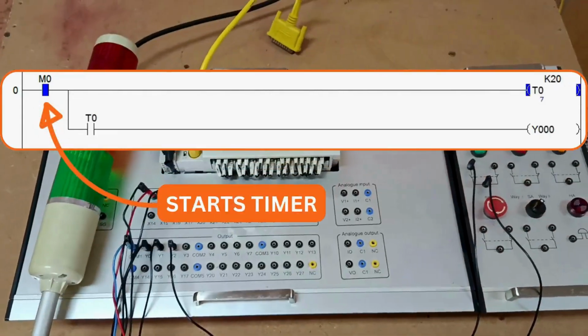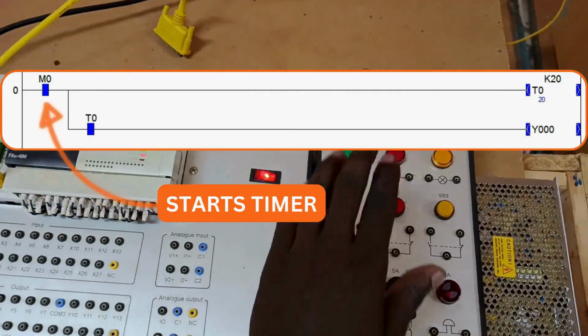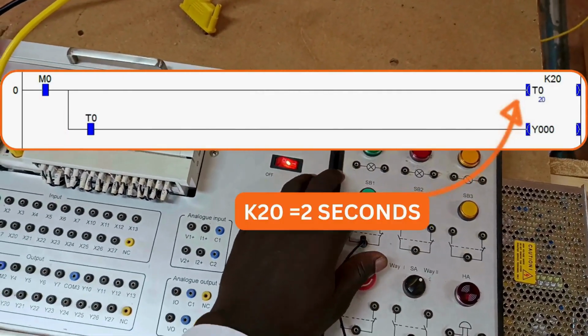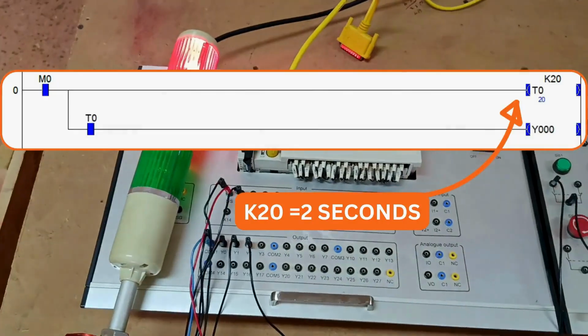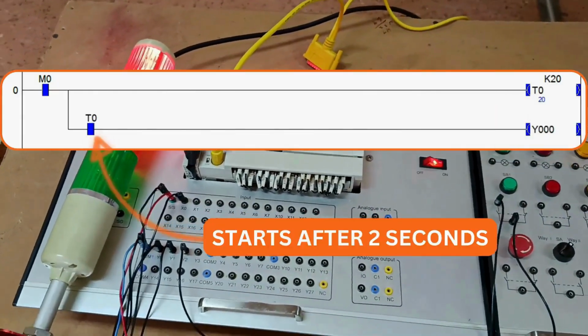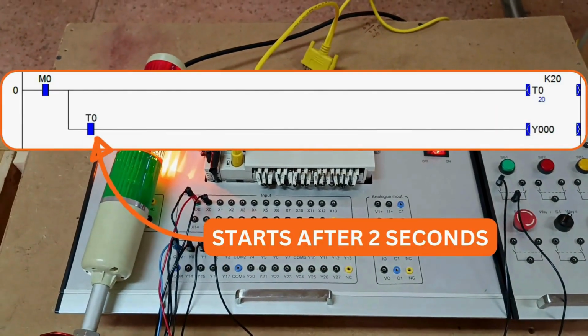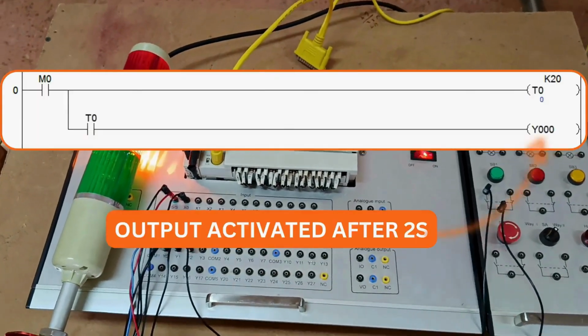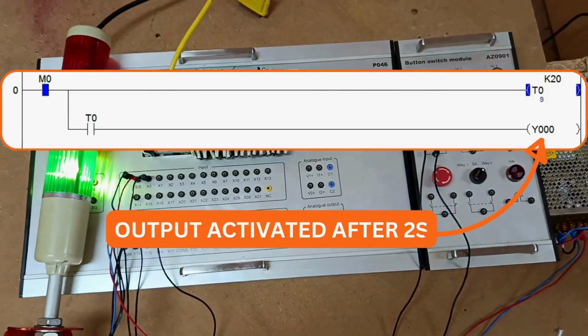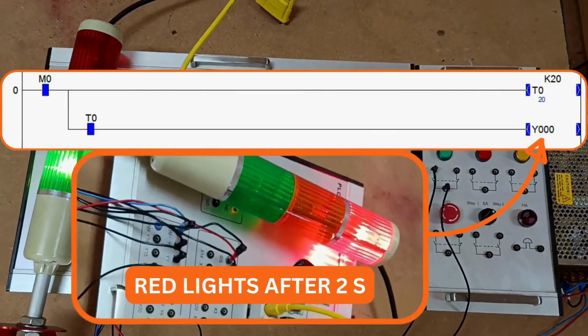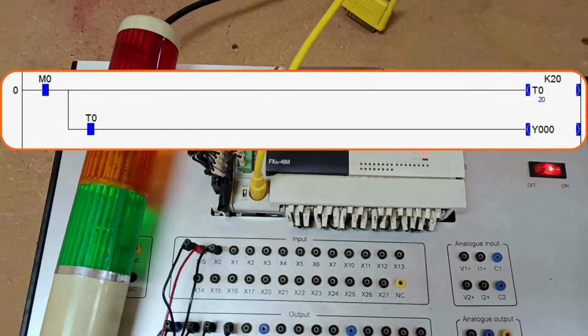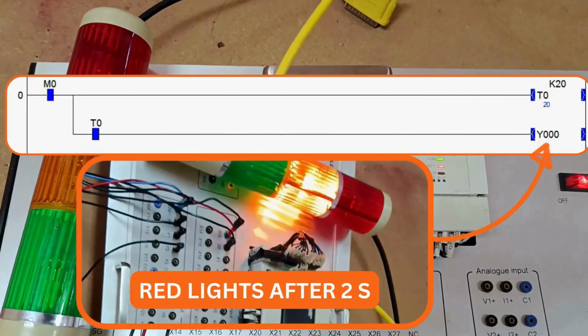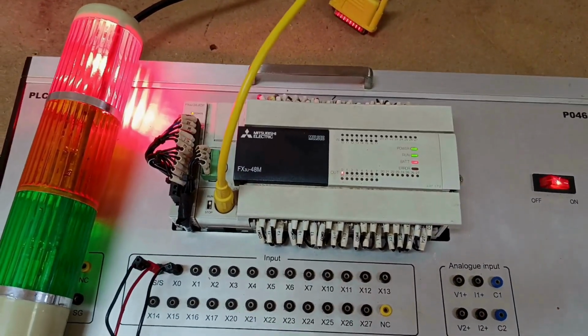M0 activates T0. Here, T0 uses K20, which represents 2 seconds in this example. The red output is Y0. The normally open T0 contact allows the output to remain active while the timer has not yet reached its preset. Once T0 reaches the preset, that contact changes state and the red lamp turns on.